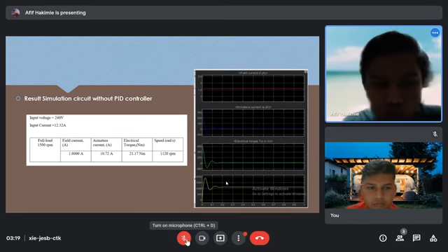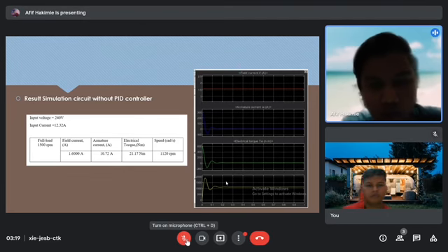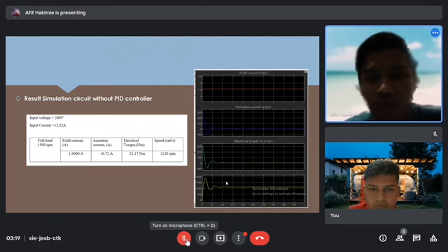And you can see the electrical torque is very high, which can cause damage to the motor if it frequently has high torque consumption. And the speed is below the safe range, which can cause high torque and high amp. So this is the result of the waveform.